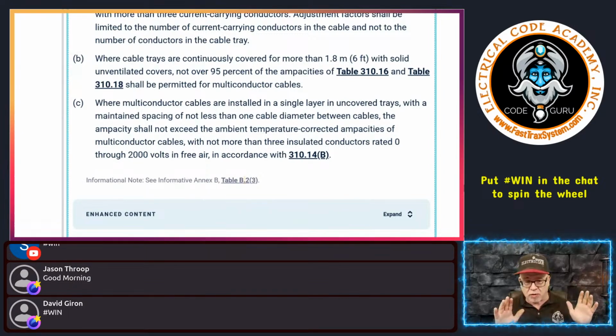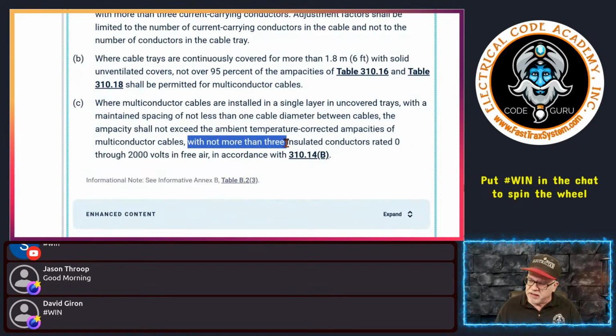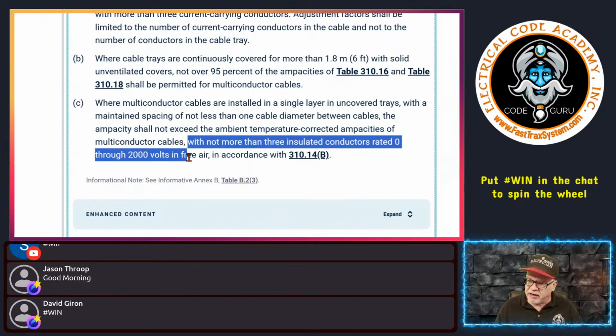You don't have bundling requirements. You don't worry about that because you are spacing. And it says we're not more than 3 insulated conductors, okay? Okay, we're not more than 3 insulated conductors rated 0 through 2000 volts in free air in accordance with 310.14(B).